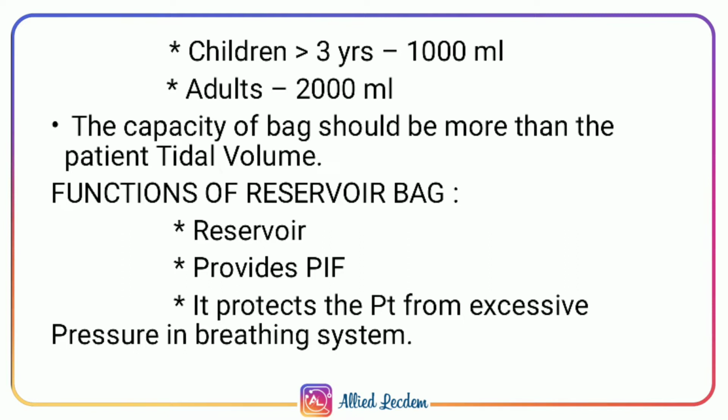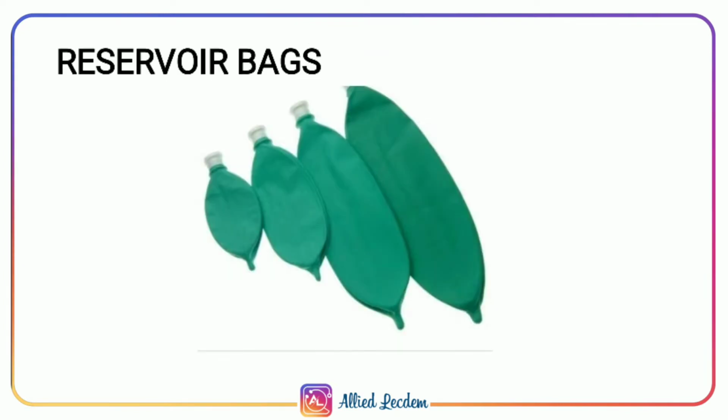The capacity the bag holds should be more than the patient's tidal volume. Tidal volume is nothing but the volume of gas inspired or expired in each breath during normal respiration. Functions: it protects the patient from excessive pressure in the breathing system, and also provides peak inspiratory flow. This is a picture of a reservoir bag with different sizes.